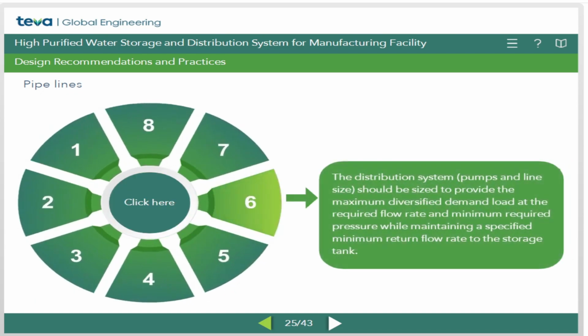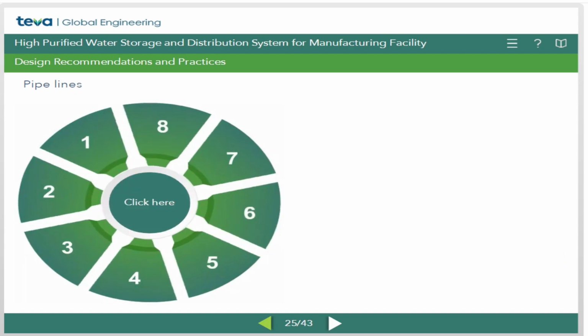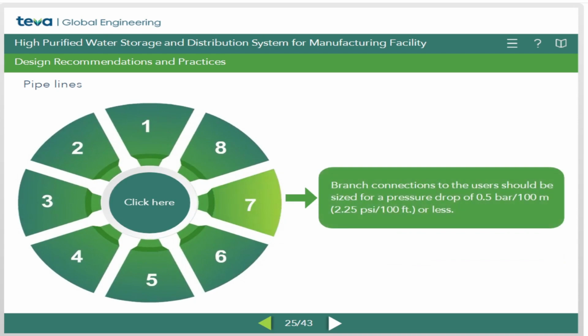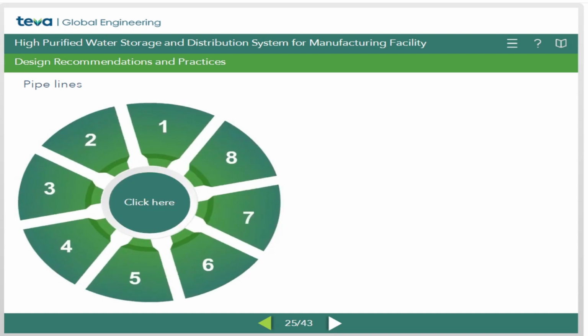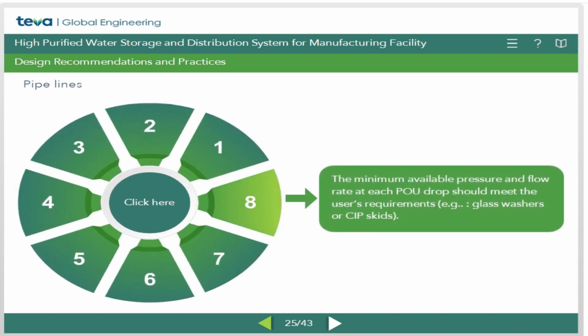The distribution system should be sized to provide the maximum diversified demand load at the required flow rate and minimum required pressure, while maintaining a specified minimum return flow rate to the storage tank. Branch connections to the users should be sized for a pressure drop of 0.5 bar per 100 meters or less. The minimum available pressure and flow rate at each point of use drop should meet the user's requirements.